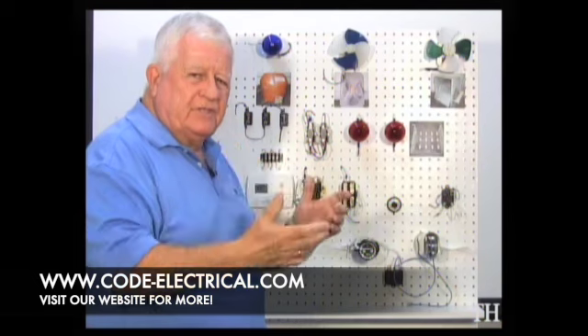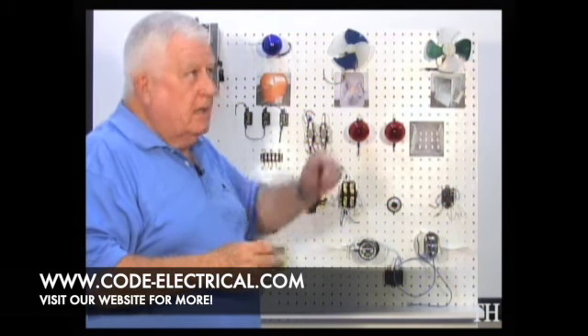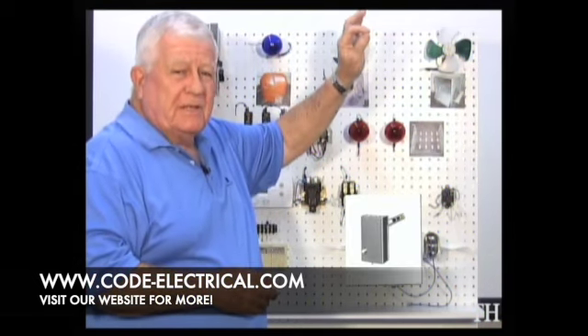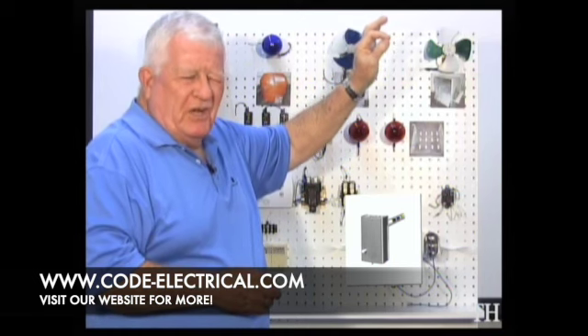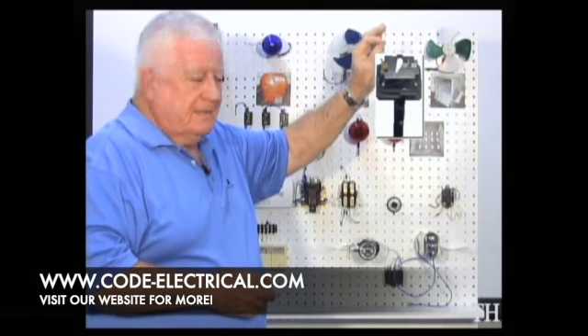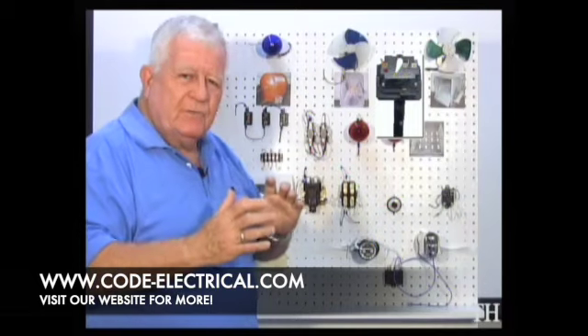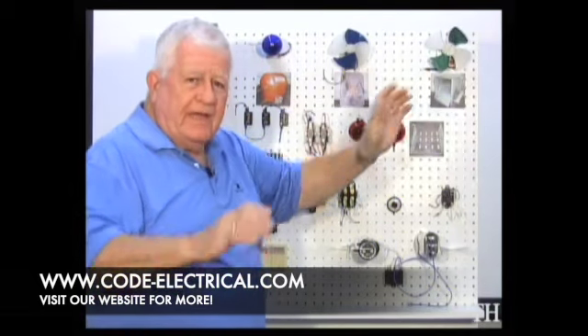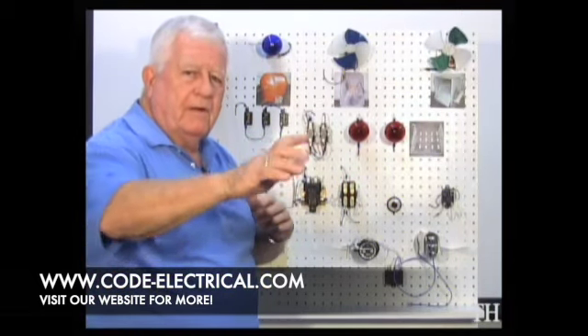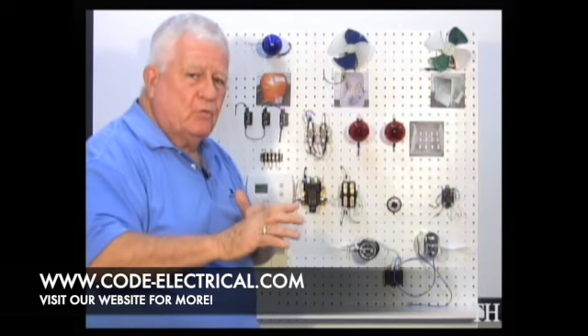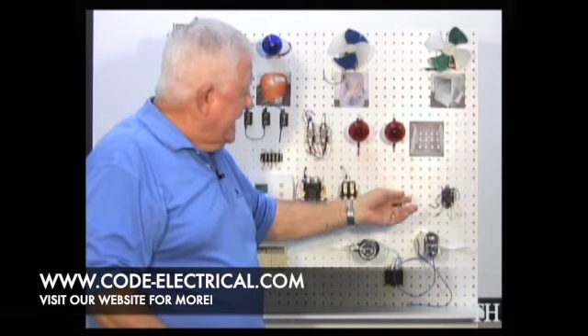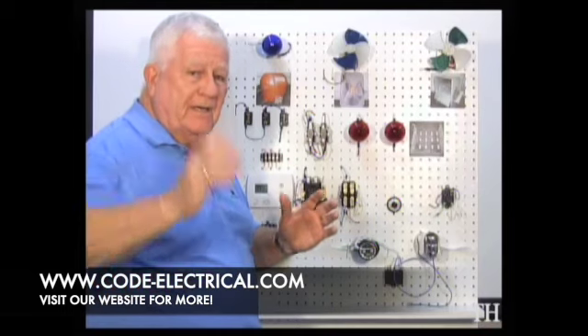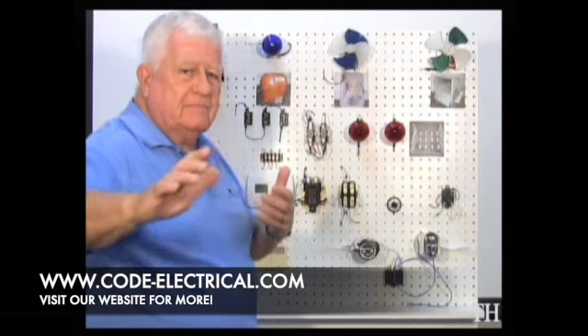But when that heat exchanger reaches temperature, like up in the plenum, there's a temperature switch. Generally, they're around 90 degrees Fahrenheit. So when this heat reaches 90 degrees Fahrenheit, now the fan comes on and I'm blowing warm air through the ductwork instead of cool air. So until this heats up, I have cool air up in that duct. So I want it warm when it comes out.